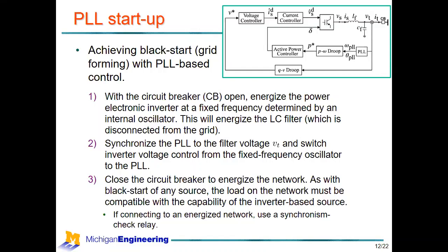Now I can synchronize the phase lock loop onto that existing voltage and switch from the fixed frequency onto the frequency of the PLL. So I've now turned on the PLL. It's still disconnected. The circuit breaker is still open, but I'm just going through a startup process to get the PLL synchronized to something. Okay, now everything's ready to go. I can close the circuit breaker, and I'm now energizing the grid or connecting to the grid. So if it's a black start, there's no load there. I close the circuit breaker and the converter starts to supply the load of the house, or whatever it might be.